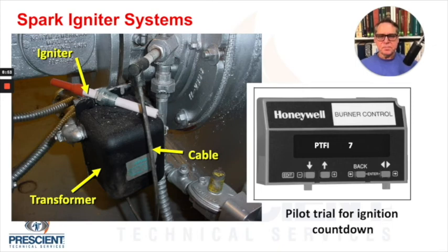Now, you will see on these displays typically PTFI, which is pilot trial for ignition, and you'll get 10 seconds to light a pilot on gas, and you should really be lighting in 2 or 3 seconds, not 10, but there'll be a countdown, and you can observe when you actually start to see that that's lit. It'll show a flame signal.